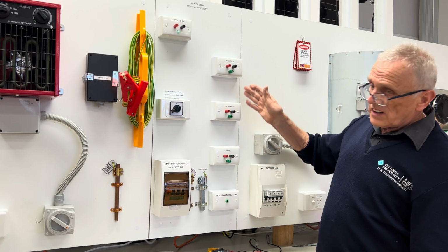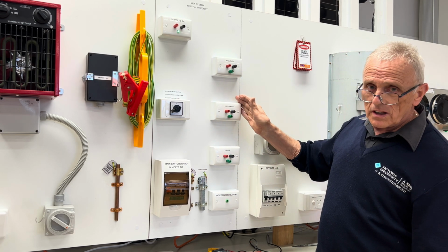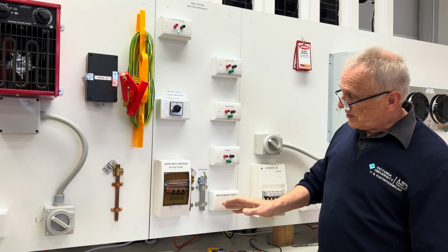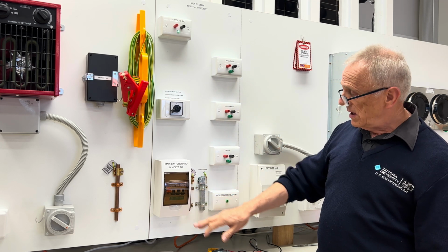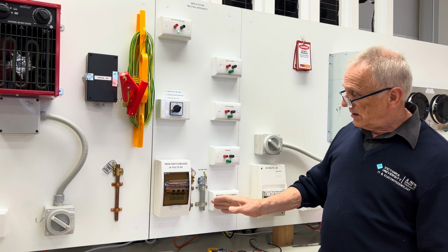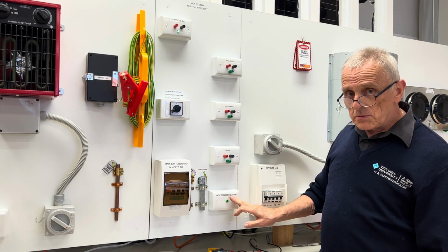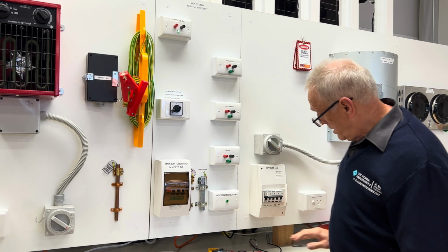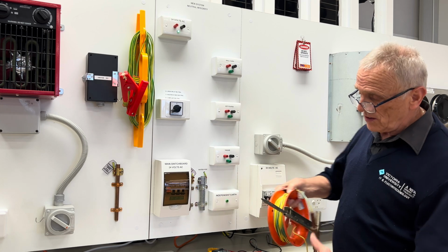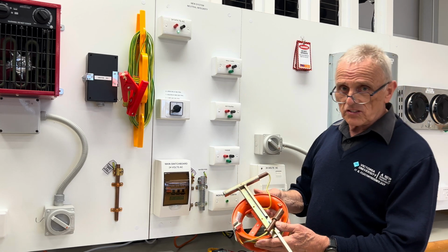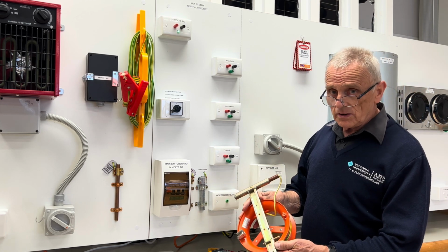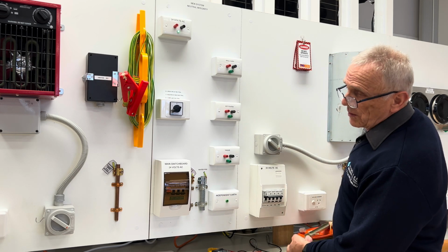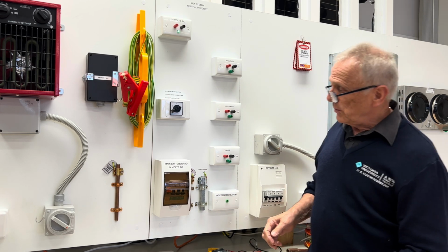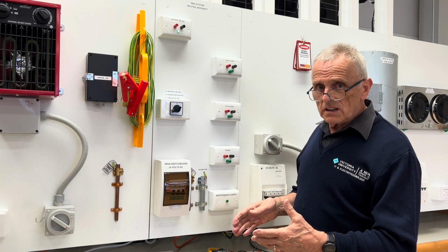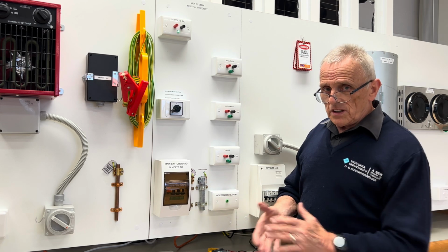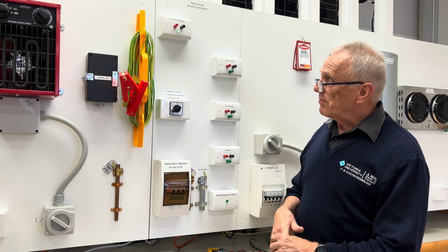We have representation of earth equipment in the installation. We've got the customer's main switchboard, the earth electrode, the water pipe, and an independent earth. This independent earth is vital because, and this is a representation of what will be used out in the field, it's vital because we don't want to interfere with the earthing system that's faulty. Therefore the independent earth comes into play.